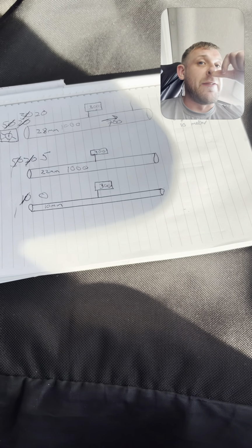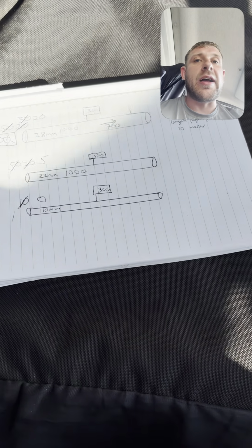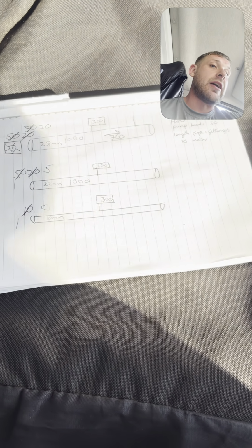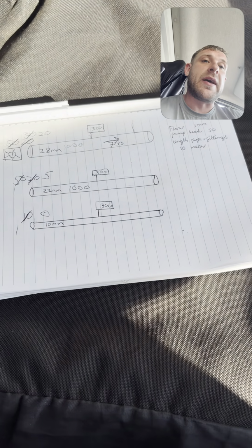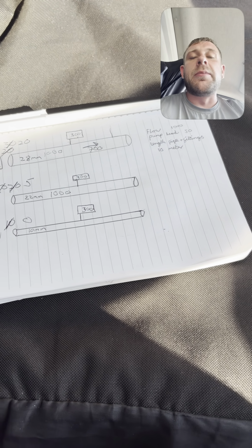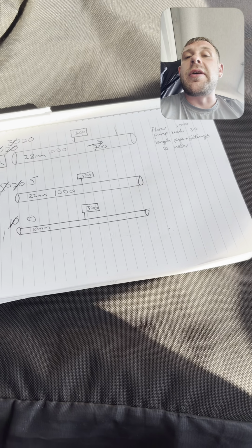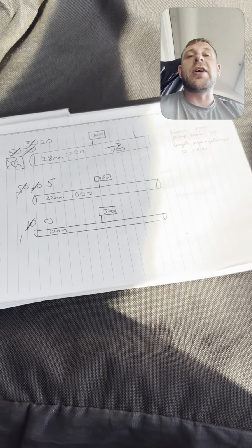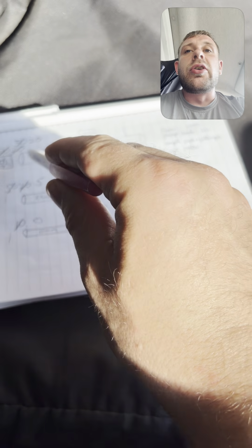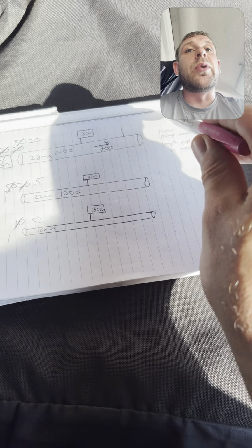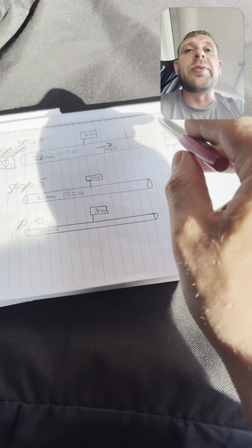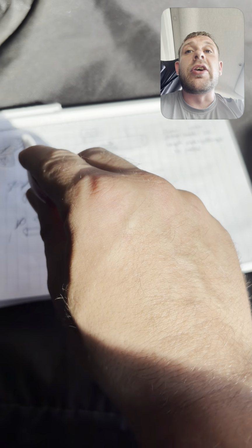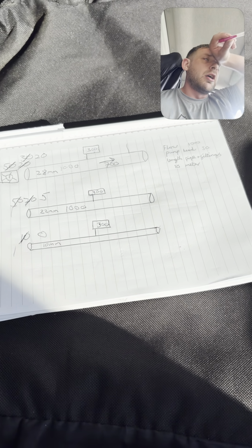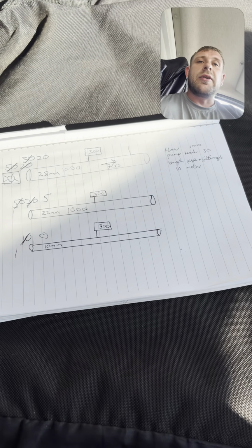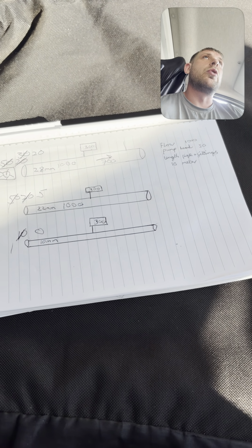And it's all relevant to how much flow rate that pipe is carrying, how long that pipe is, and how many fittings are on it, and you're going to lose different amounts of that pump head. But with 10mm pipe, as long as you can get to that furthest away radiator, the majority of the time the furthest away radiator, and you've still got some of this pump head available, then your 10mm pipe is absolutely fine. We've got systems with 10mm pipe on loads and loads of jobs.